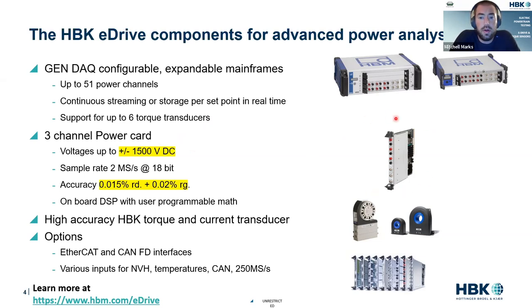The electric power measurement card is probably the star of the show. It handles up to 1500 volts DC. And we do have some future solutions coming out that will take up to 2 kilovolts DC directly. Sample rate is up to 2 megasamples per second. I'd love to speak at depth about sample rate. Honestly, this is even overkill for electric power. 1 megasample ends up being really the sweet spot because of the limitation of current sensors on the market. So from a bandwidth perspective, 2 megasamples buys you more than enough to get a really, really accurate power measurement.